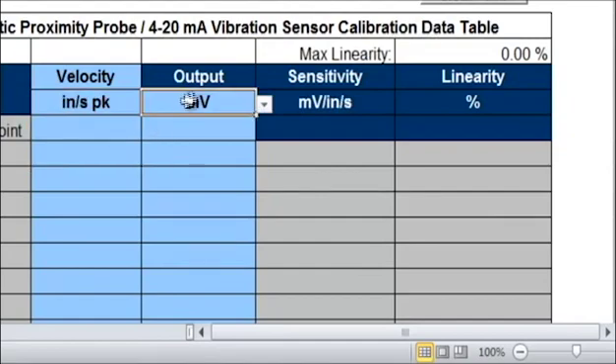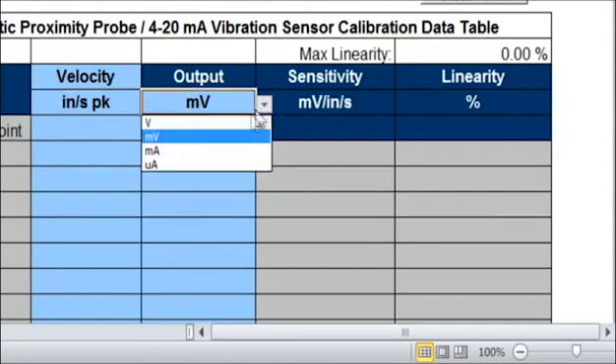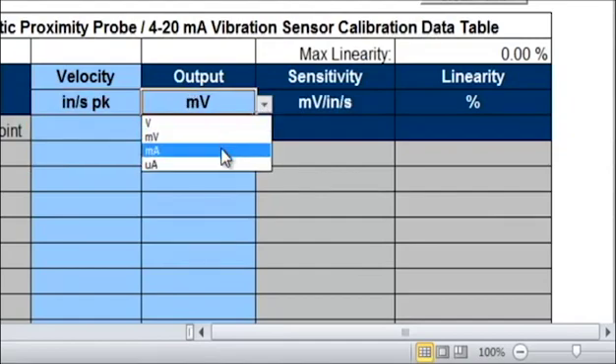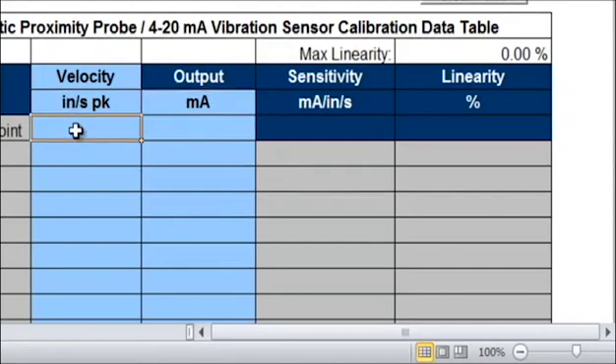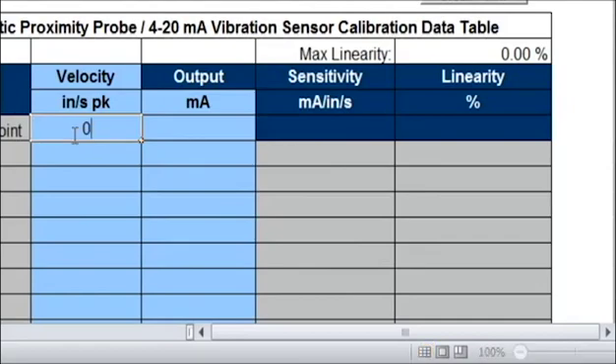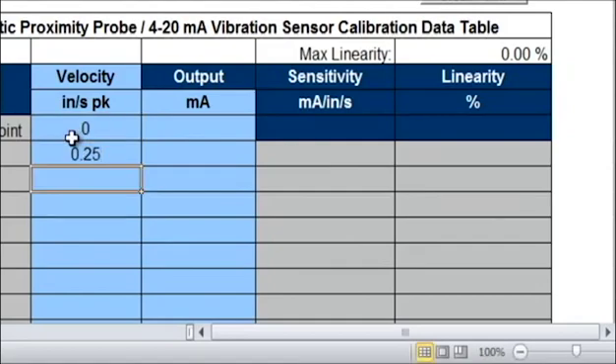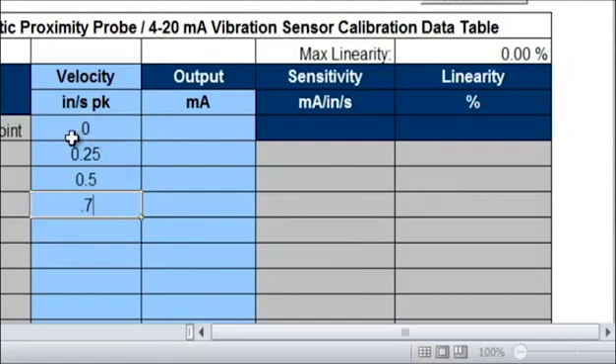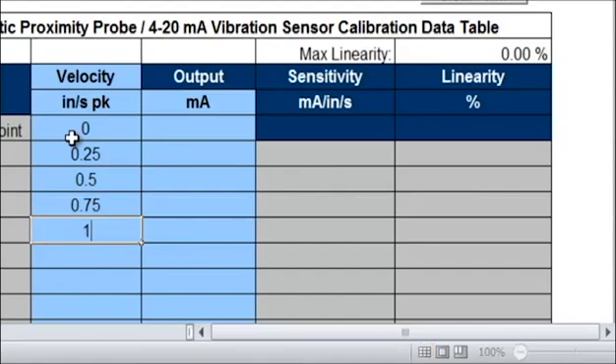Our output is in milliamps. We do want to test over 5 points through the sensor's range so that we can confirm that the sensor's response is linear through its entire range. So we'll start at 0 inches per second peak, then 0.25, 0.5, 0.75, and 1 inch per second peak. And now we're all set up and ready to start taking data.